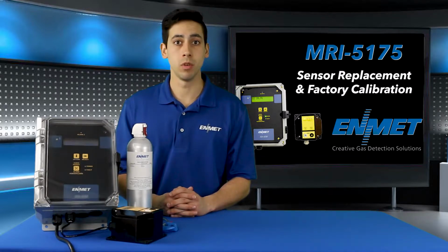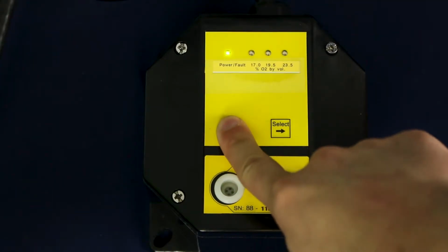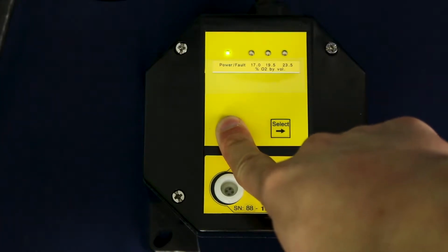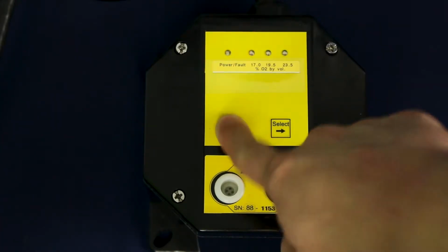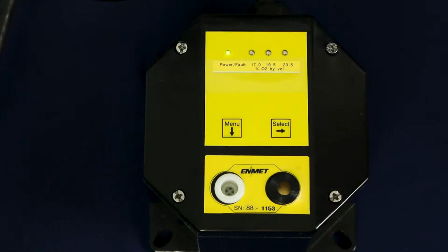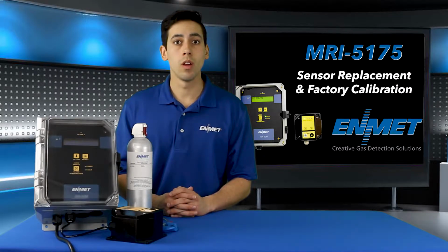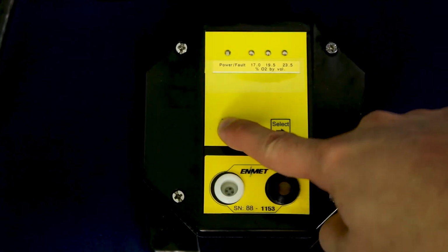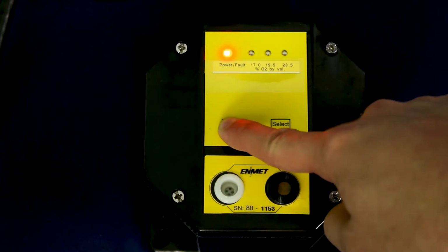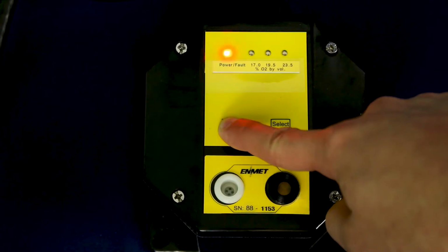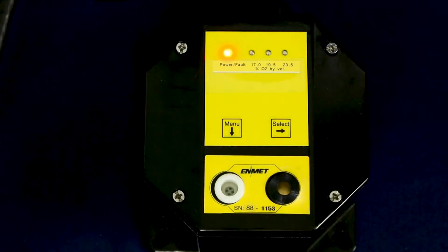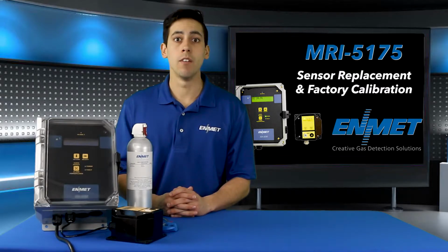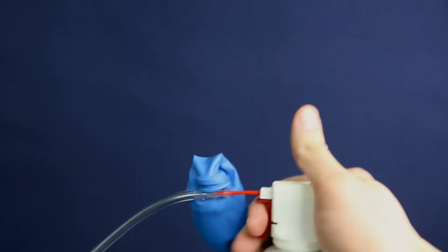Press and hold the menu switch for 3 to 5 seconds. The power fault LED will flash red green, red green, red green on repeat. You will now press and hold the menu switch for 3 to 5 seconds again. The power fault LED this time will flash a sequence of red, red, red on repeat. This step puts the instrument in a factory calibration mode for the new sensor calibration.